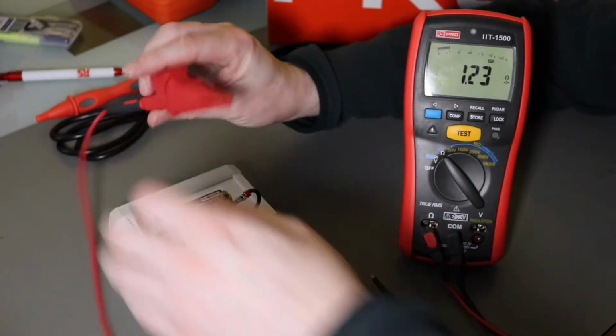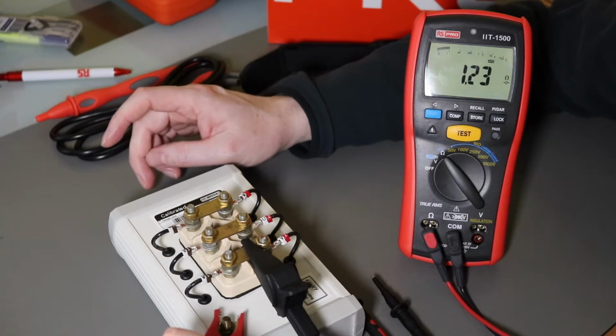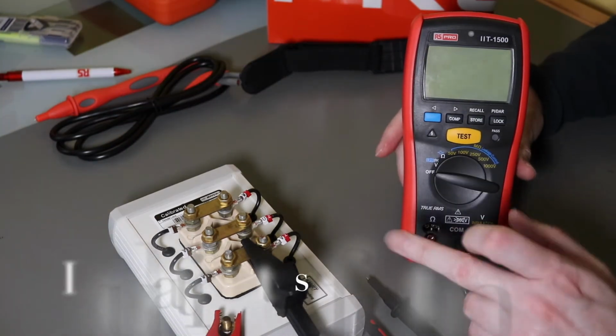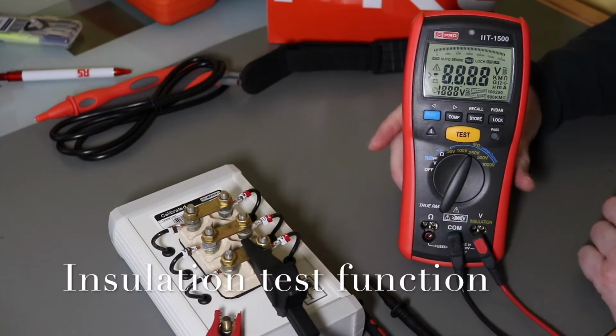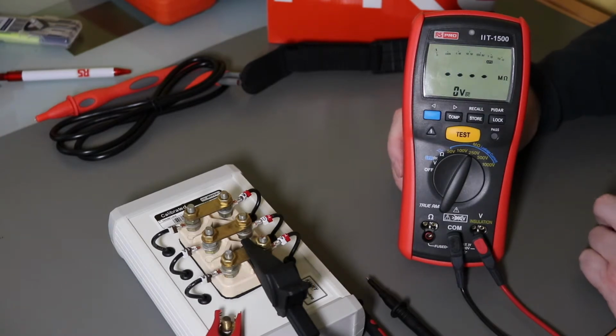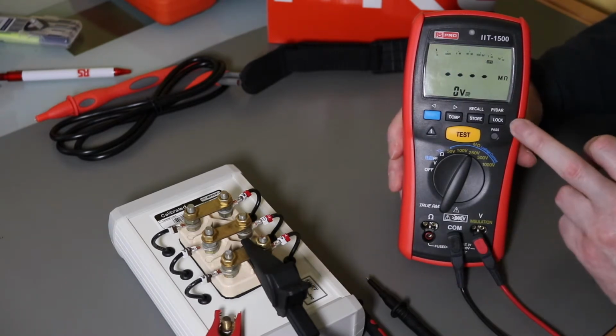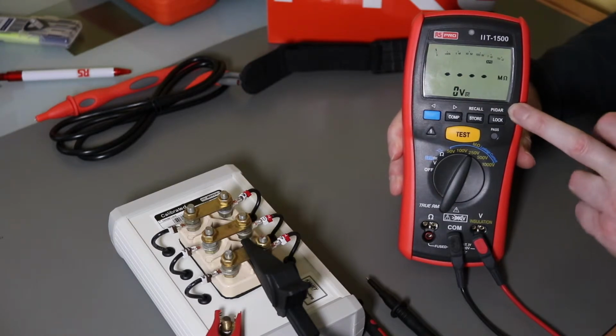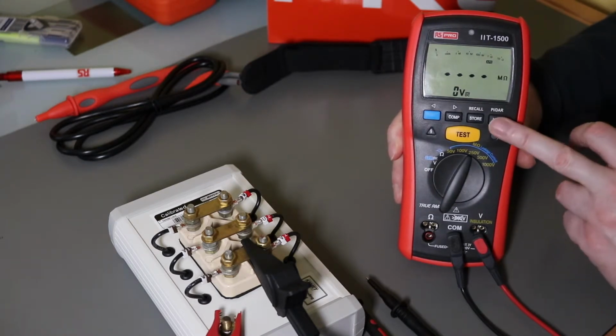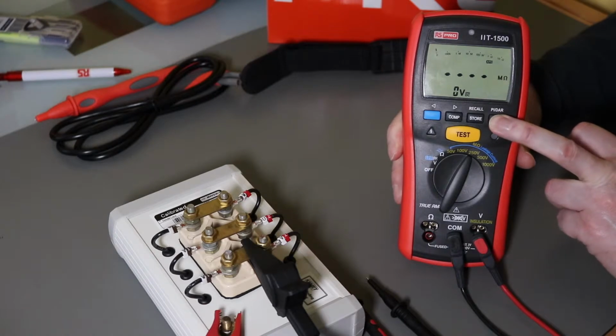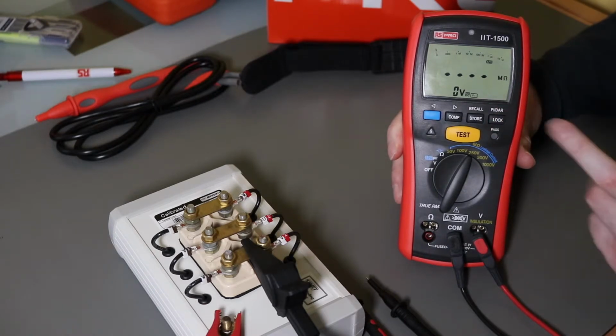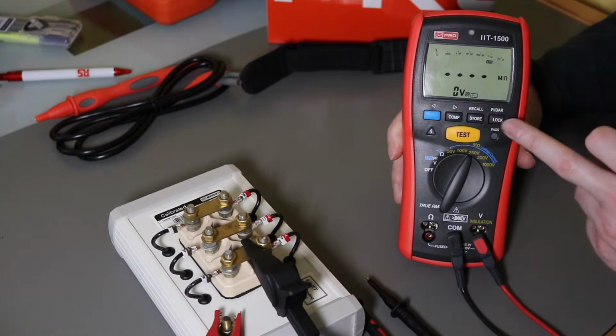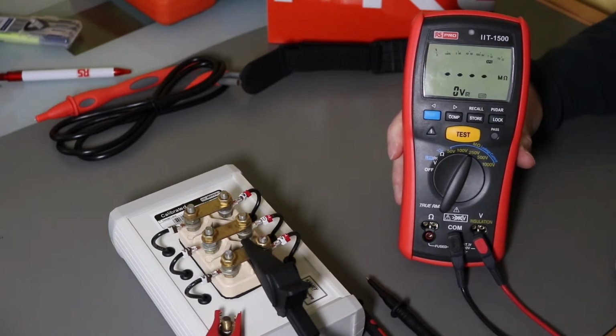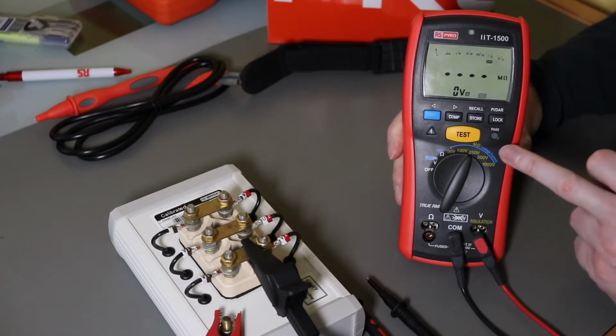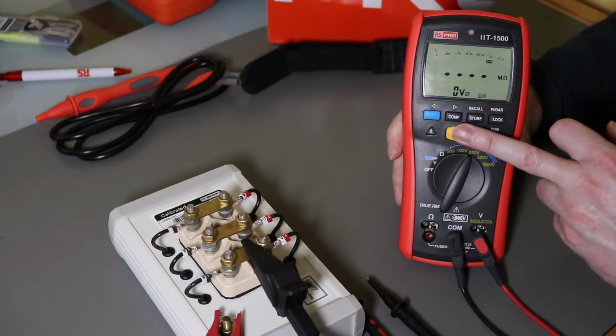Let's go back to insulation, which was what I was going to do first time round. Set it for insulation test. Go down to 50 volts on this particular one. You have the polarisation index and DAR facility here. To get to them, you press and hold the lock until the little PI turns up, so it goes to polarisation index first. If you want to get to dielectric absorption ratio, press it again, short press, and it gets to that. And then you can click and hold test.